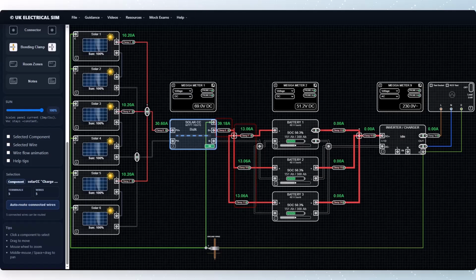into each battery. In the simulator, each battery has a built-in battery management system, and the batteries communicate with each other. If one battery is at a different state of charge, the system can reduce or throttle the current into that battery as it gets closer to full charge, helping all 3 batteries reach 100% together. We can see this by using the manual battery slider on each battery and setting each one to a different state of charge. Each battery then shows a different current value. With a modern BMS and compatible equipment, this type of current management can also happen in real systems.